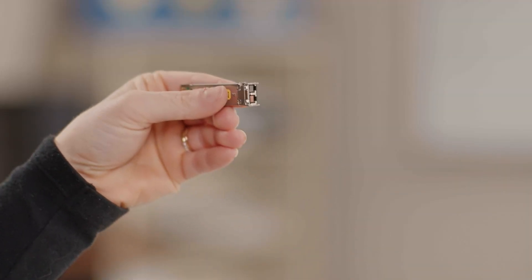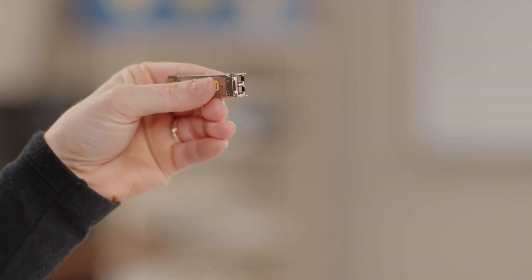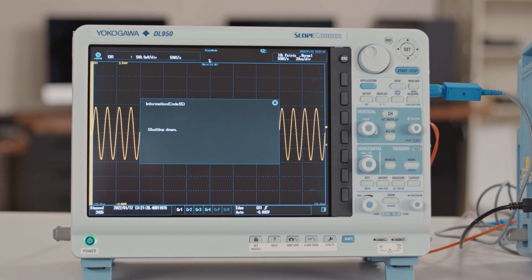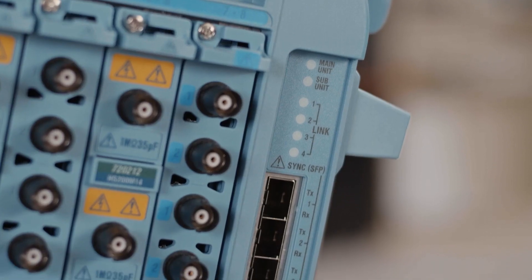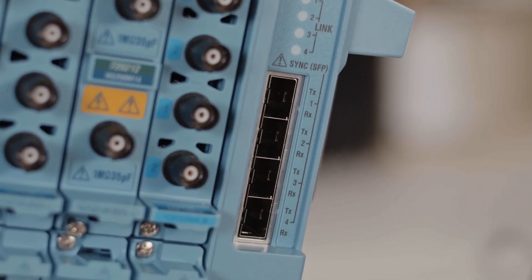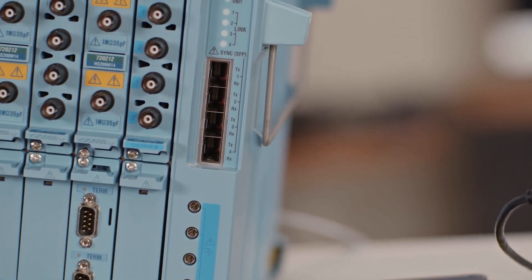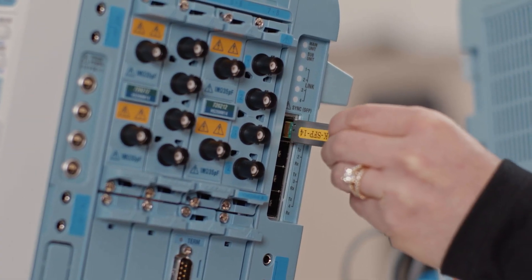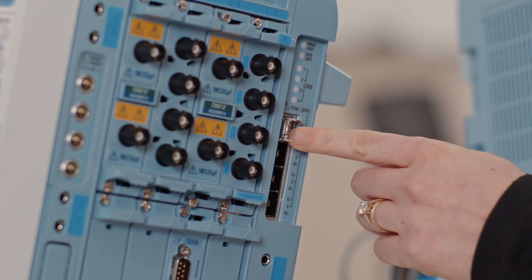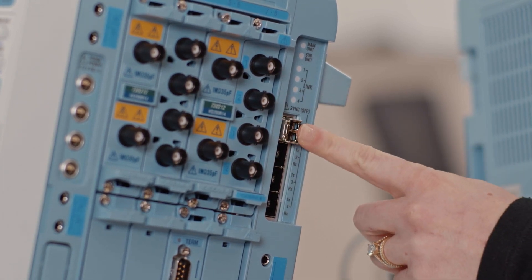To make the physical connection between multiple DL950s, you'll need to install the SFP modules and connect the optical cords. To install the SFP modules, start with the DL950s turned off. Insert the modules into the link connectors on the right side of the instrument. Tilt the latch lever down and align the SFP module with the guide on the link connector. Slowly push it in until you hear a click.